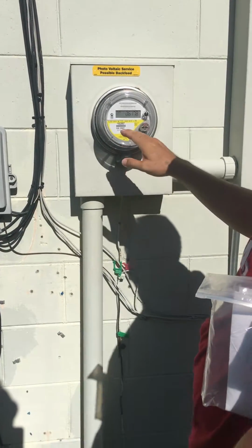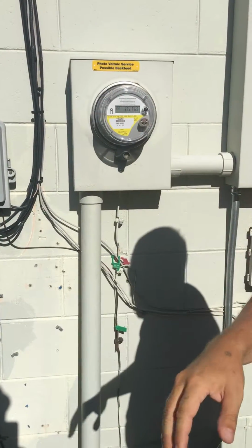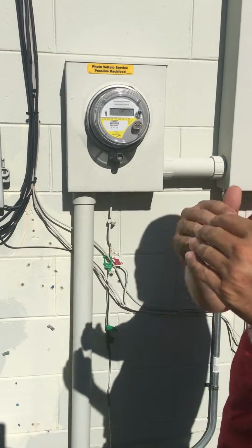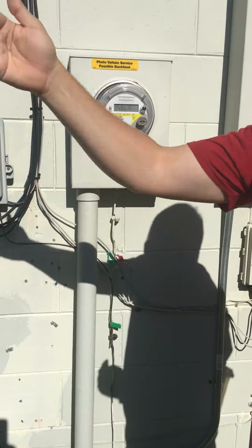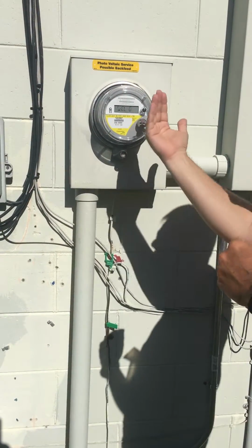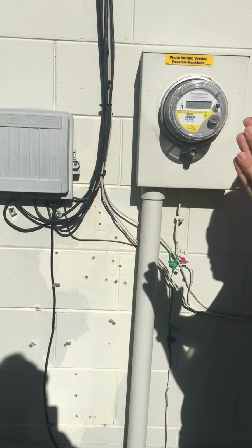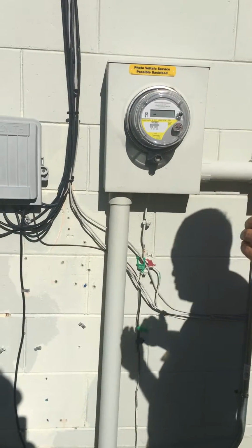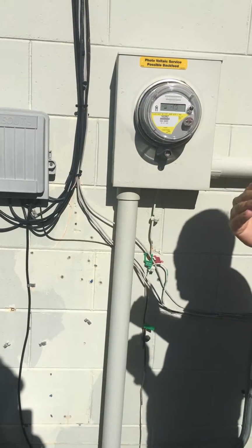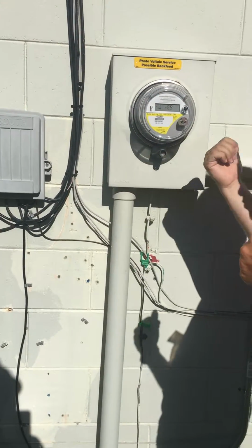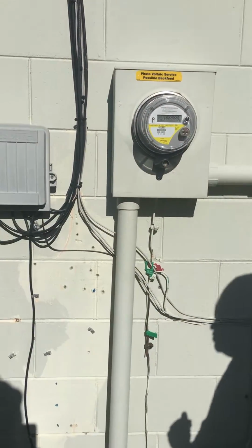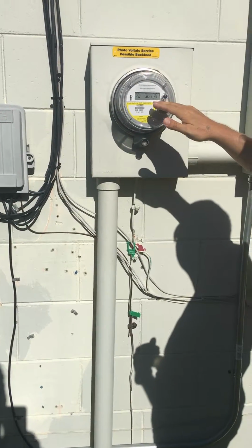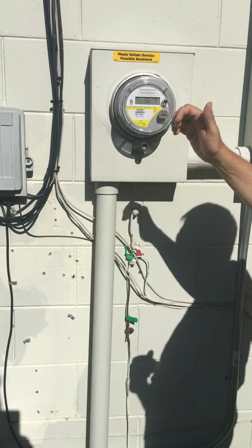Right now we're making 3,500 watts. If my AC kicks on, or I have my oven on or something like that, and my house needs, say, 5,000 watts, it gets 3,500 from the solar and the utility feeds in the other 1,500. Once I turn off the appliances and my house usage goes down to 2,000, with my solar still doing 3,500, 2,000 from my solar is going in my house and 1,500 watts is going back to the power company. All day long, it's going in and out through here. You'll see the meter going backwards, you'll see it stop, you'll see it going forward.